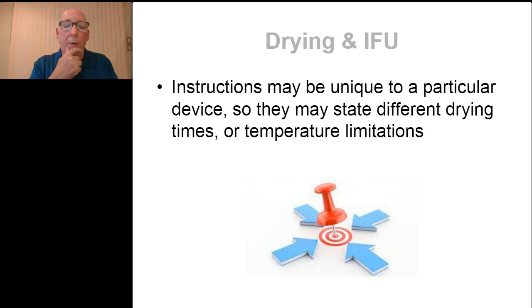So again, drying and IFUs. In addition, a manufacturer may recommend several methods for drying a device, and you can determine which methods are best for your department. Always start with your IFU, and they'll let you know relative to drying times, if those are listed, as well as any temperature limitations, especially if you're using a mechanical drying process such as a drying cabinet for scopes and other materials that may have temperature limitations. Refer to those IFUs for what those temperature specifications are for that specific device.